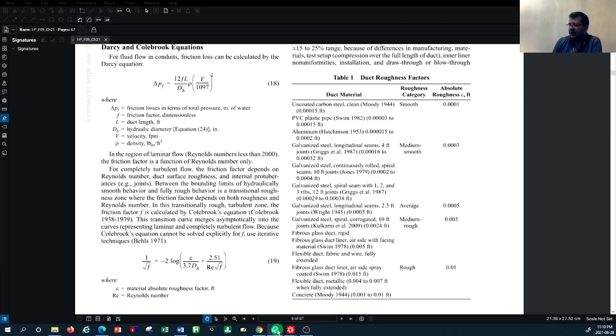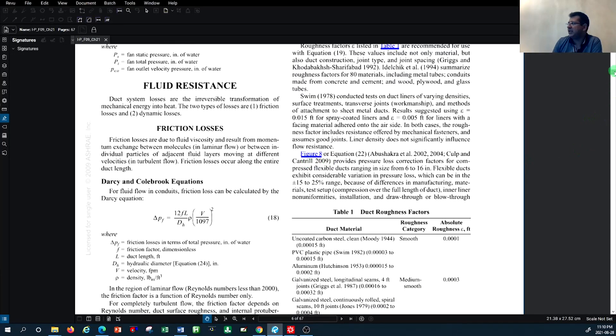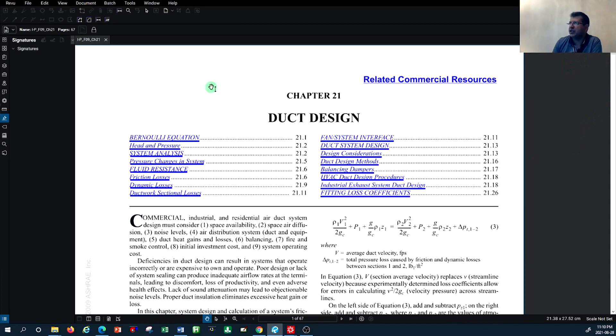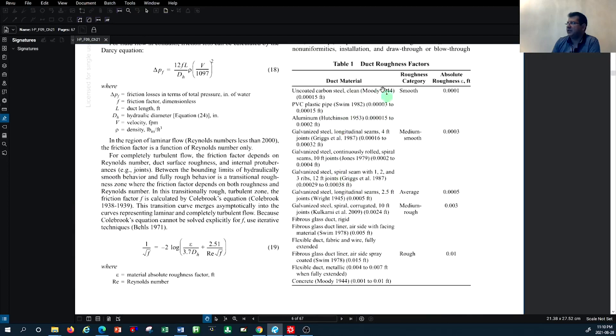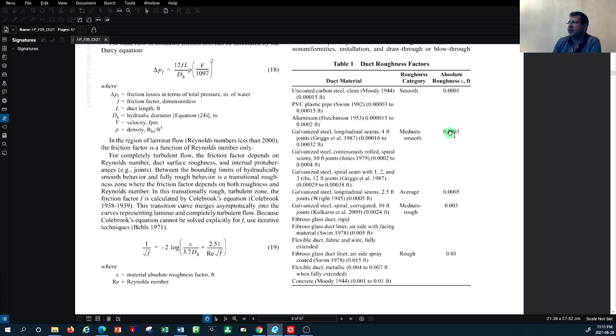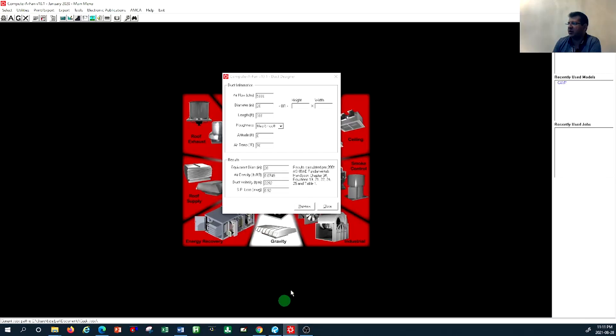I'll quickly show you where this is referenced. Using ASHRAE 2009 Fundamentals, the duct roughness table shows that depending on the type of material — for example, galvanized steel is considered a medium smooth material for duct roughness — this correlates to an absolute roughness value. In our case I'll keep it as medium smooth and go back to the software.